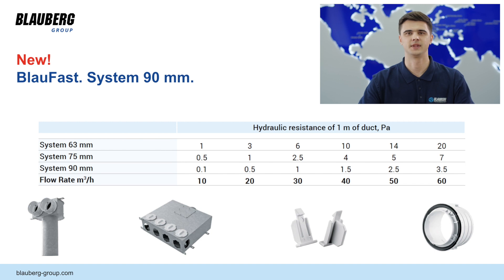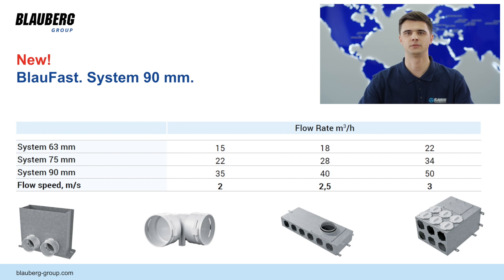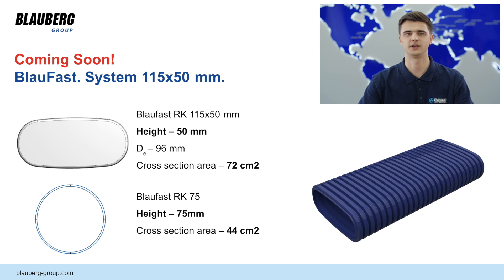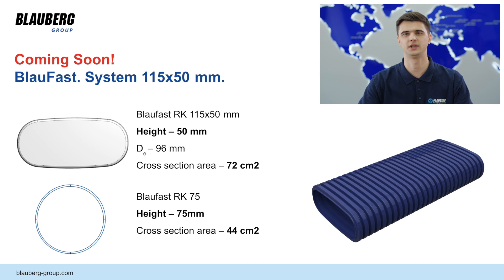The 90 mm system is designed for lowering hydraulic resistance in duct systems with complex routing. At different flow rates, the 90 mm system has minimal hydraulic resistance. You can also use the 90 mm BlauFast system to reduce air speed in your distribution system, which means reducing noise from moving air. Another new member of the BlauFast family is the oval system 115 by 50 mm, specially designed to reduce the space occupied by the duct system. The oval system requires less space but has a cross-section area almost twice as large as the 75 mm BlauFast system. All systems are provided with a full spectrum of fittings, plenums and accessories.